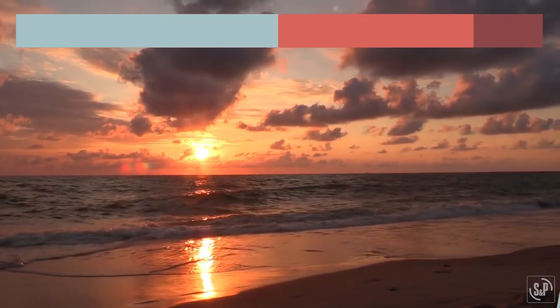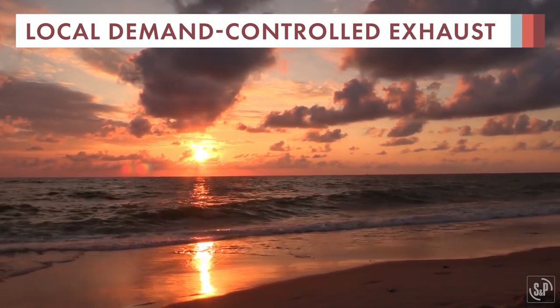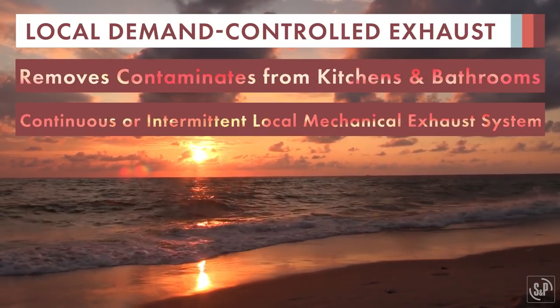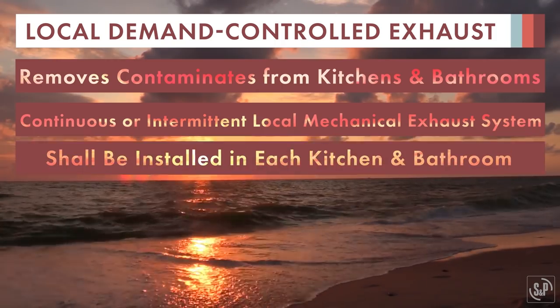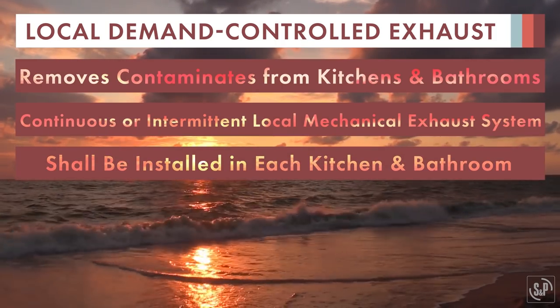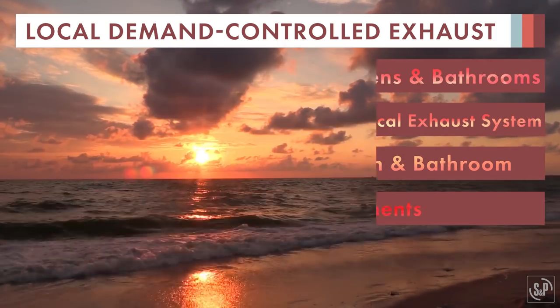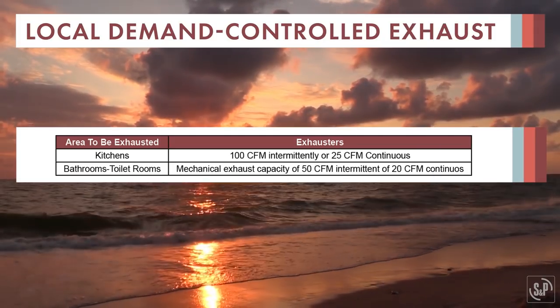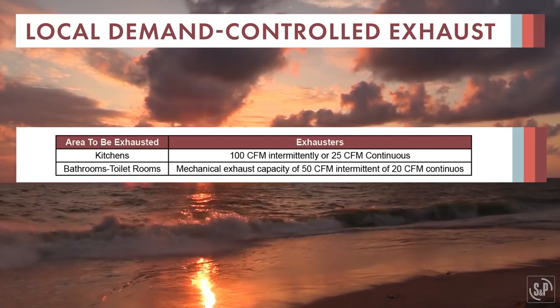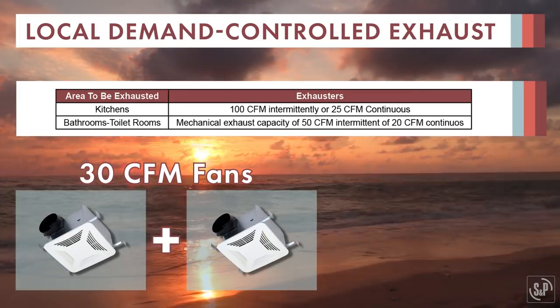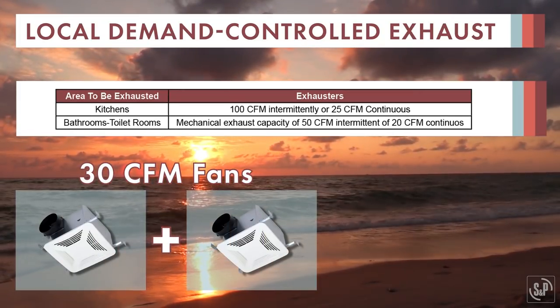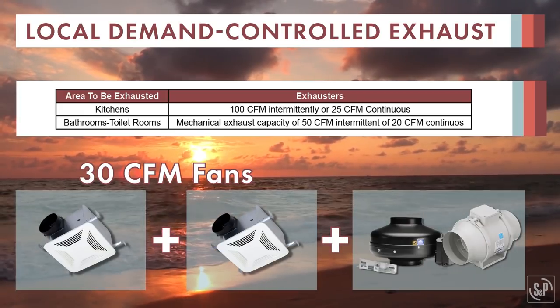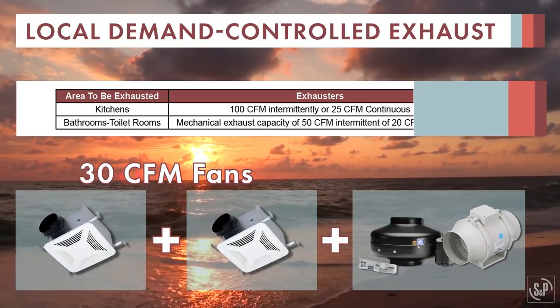The second basic requirement, local exhaust, is intended to remove contaminants from kitchens and bathrooms. A continuous or intermittent local mechanical exhaust system shall be installed in each kitchen and bathroom and meet the CFM requirements in this table. Remember, the local exhaust fans do count towards the whole house ventilation requirement. For this example, two 30 CFM bathroom exhaust fans running continuously would meet the ventilation requirement, in addition to a 100 CFM intermittent range hood in the kitchen.